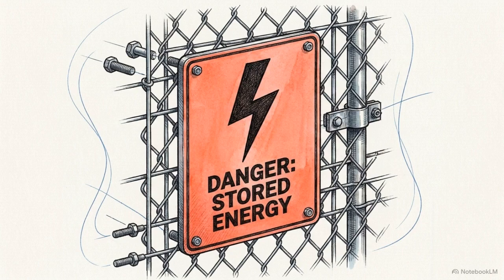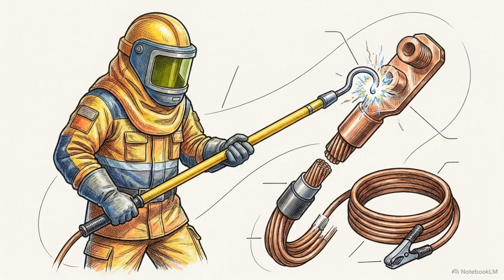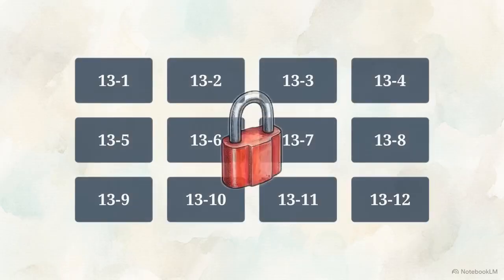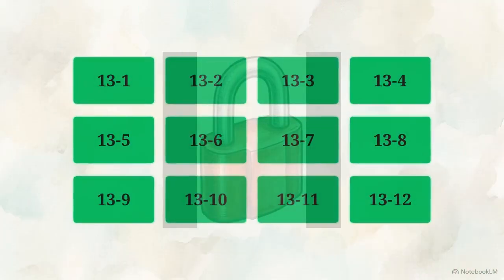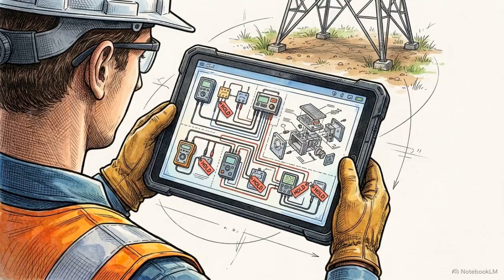After applying direct current in any phase test, technicians must use grounded discharge sticks to completely clear stored capacitive energy before proceeding. By locking in these baseline isolation and discharge protocols, technicians can execute tests 13-1 through 13-12 by focusing exclusively on the unique electrical variables, instrument configurations, and required hold points of each specific procedure.